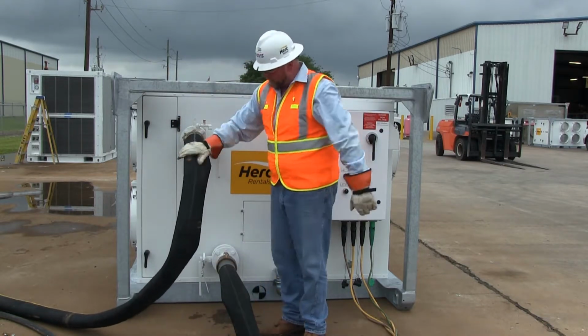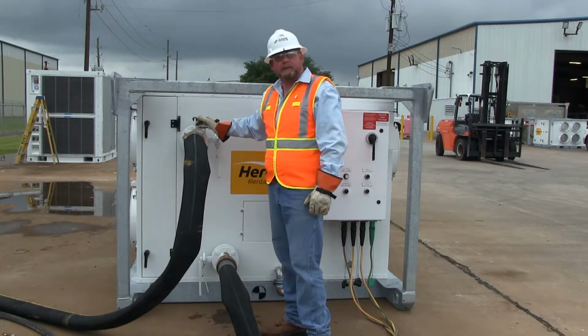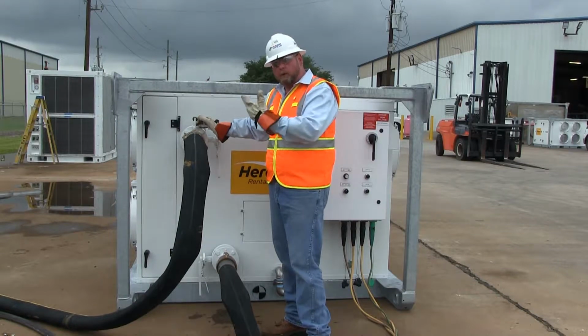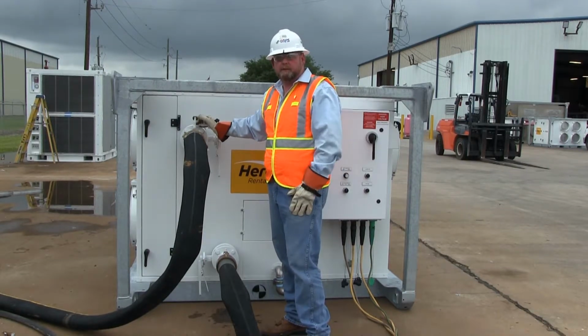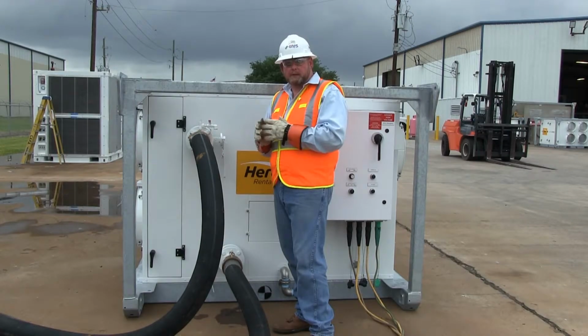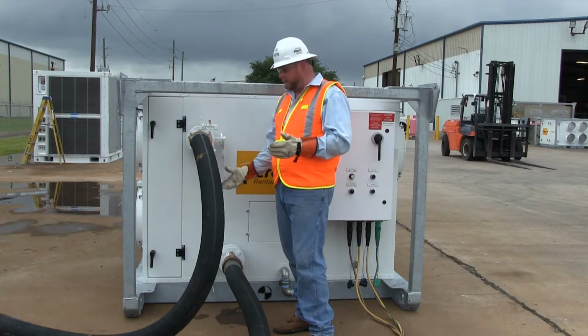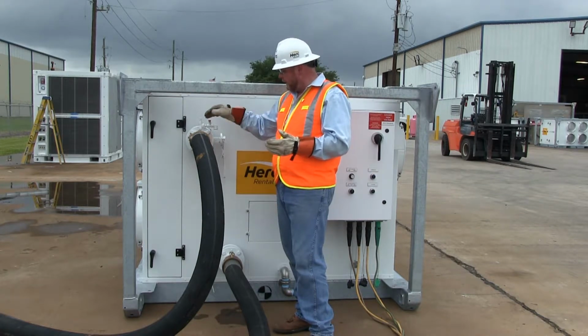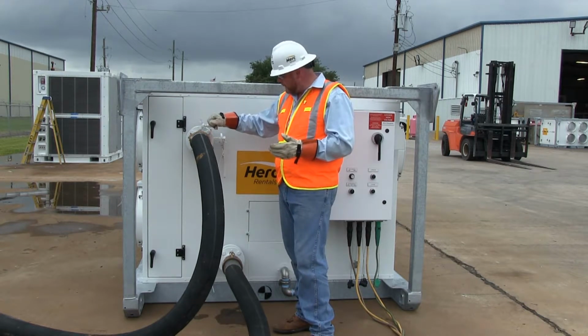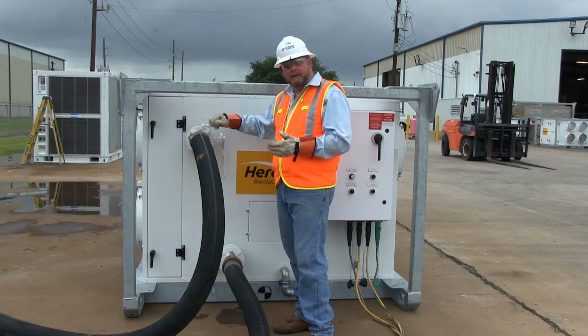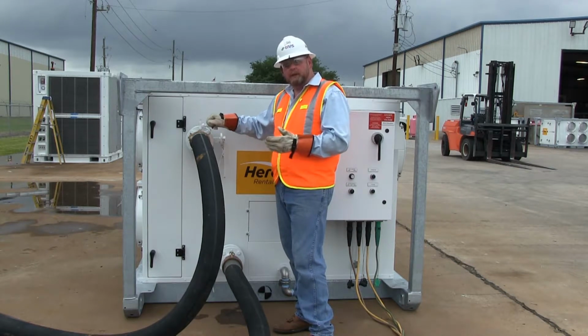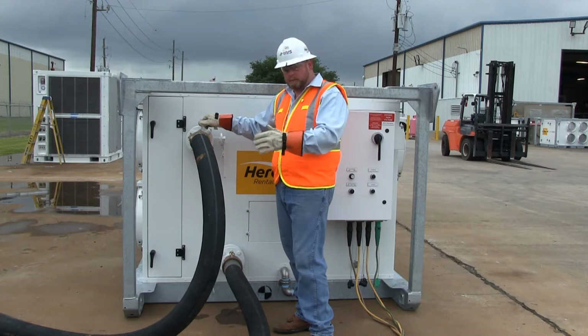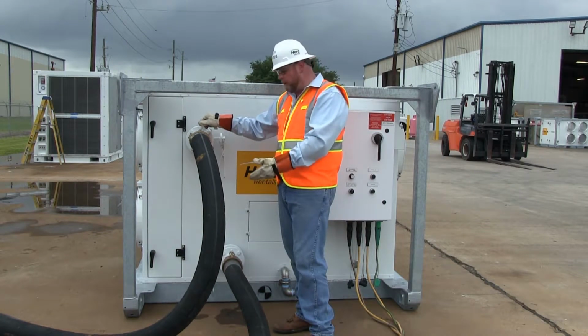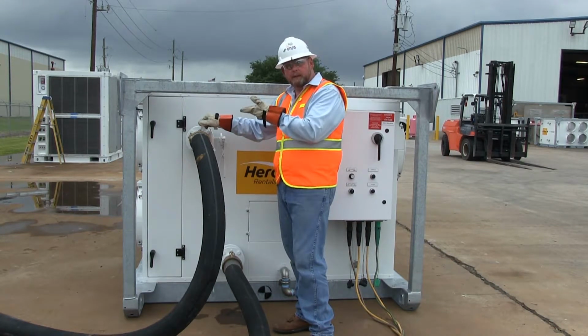Now we're going to fill up our system, and we're going to bleed the air off the top here, and that'll get our coil full of water so that we can use it for transfer heat. We filled our system up, pressurized it to about 45 psi. We pushed out the water from the bottom up to the top, and your final air bleed points right here at the top. You'll hear the air coming out on there, and you'll continue to bleed that air out while filling the system up, and all the water will go to the bottom, all the air come to the top.